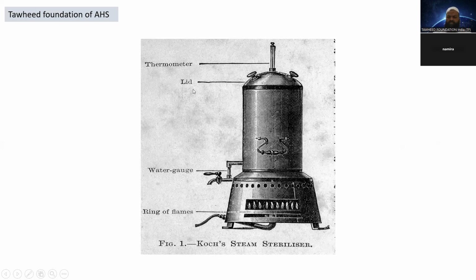Lid. The lid seals the top of the sterilizer chamber. Its function is to keep steam from escaping and maintain pressure and temperature. The lid is typically tightly secured and may include blow-off valves for safety. These valves, two valves. Water gauge. The water gauge shows the water level inside the device. It allows the user to monitor and adjust water content, ensuring enough is present to generate steam throughout the sterilization process but preventing overflow.